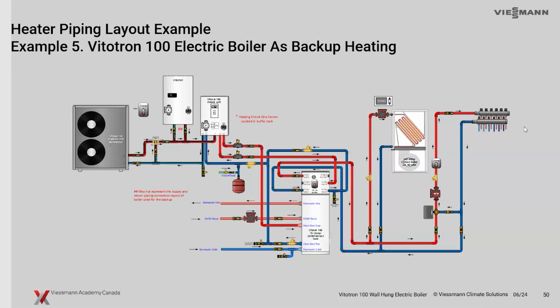You can see this is the full gamut of our little air-to-water heat pump: the outdoor unit, the indoor unit, and the electric boiler sitting beside it. But we add a buffer tank in there. It can do domestic hot water. We have multiple temperature capabilities with the mixing valve function off of that little heat pump as well, so you can really expand your system here.